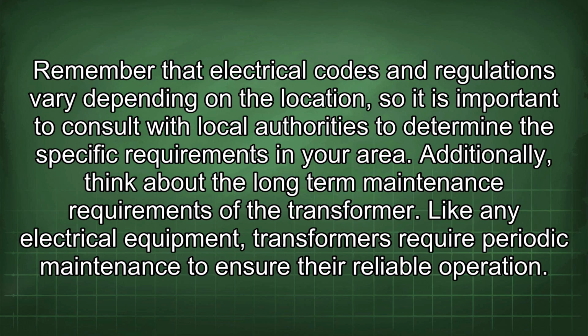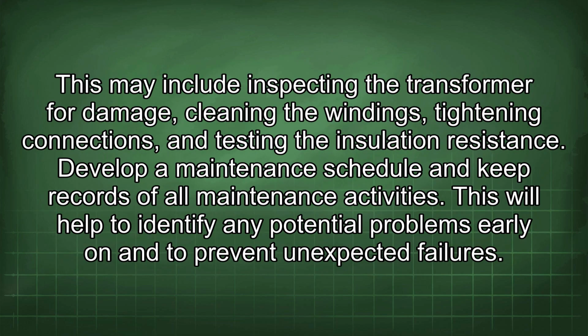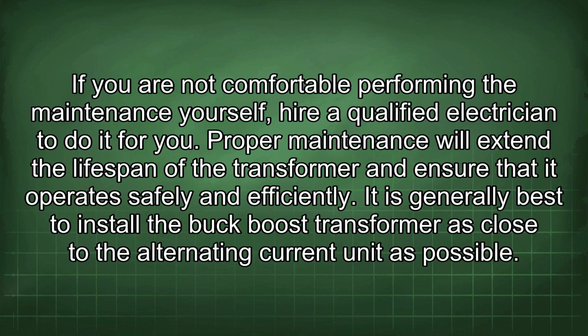Additionally, think about the long-term maintenance requirements of the transformer. Like any electrical equipment, transformers require periodic maintenance to ensure their reliable operation. This may include inspecting the transformer for damage, cleaning the windings, tightening connections, and testing the insulation resistance. Develop a maintenance schedule and keep records of all maintenance activities. This will help to identify any potential problems early on and to prevent unexpected failures. If you are not comfortable performing the maintenance yourself, hire a qualified electrician to do it for you. Proper maintenance will extend the lifespan of the transformer and ensure that it operates safely and efficiently.